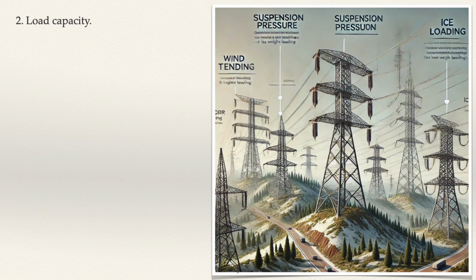Load capacity. It is another crucial factor in the design criteria of transmission lines, as it defines the line's ability to handle electrical power safely and efficiently without overheating or experiencing excessive sag. 1. Power demand. The load capacity is determined by the amount of power the transmission line is required to carry, measured in megawatts, MW. This depends on the load centers, cities, industries, or regions, and their projected energy requirements. A transmission line with inadequate capacity can lead to overloading, increased line losses, and a higher risk of power outages.